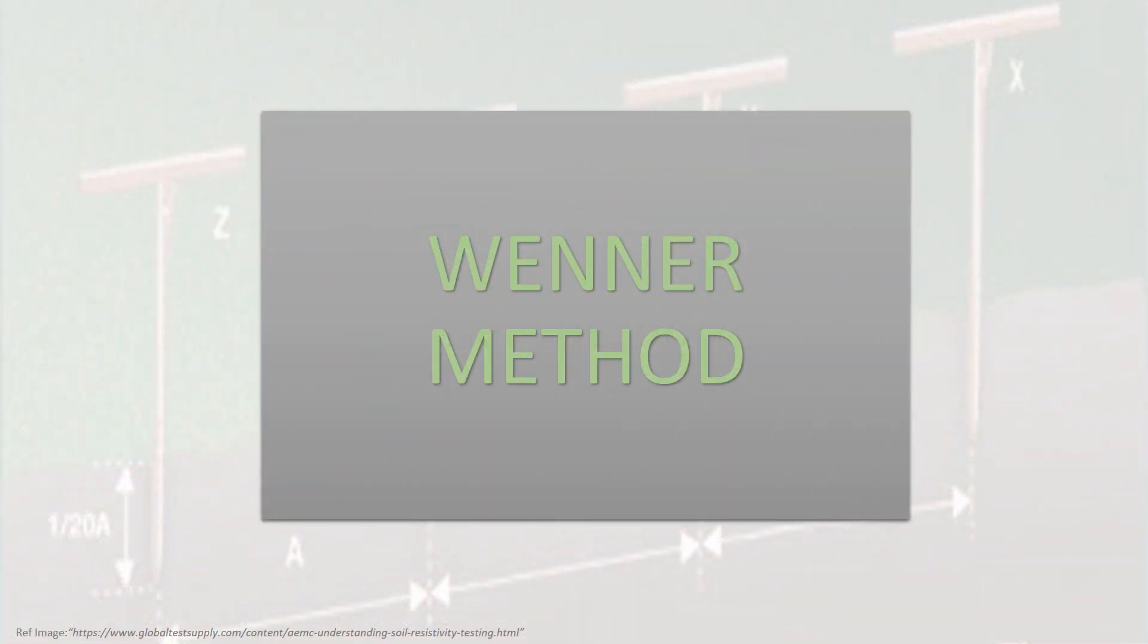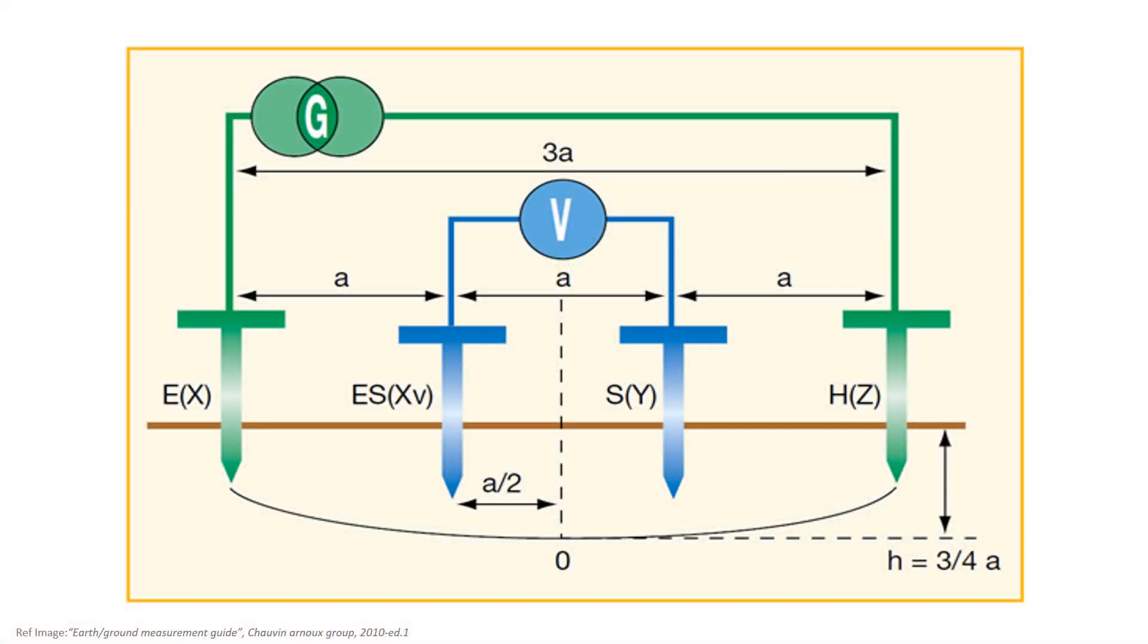Let's start with the Wenner method. Measurement principle of Wenner method is based in four electrodes that are set up in line in the ground, equally spaced at a distance A from another. As we can see here, a generator is used to inject a measurement current between the two outer electrodes, called current electrodes, and we measure the voltage between the two internal electrodes, called potential electrodes.